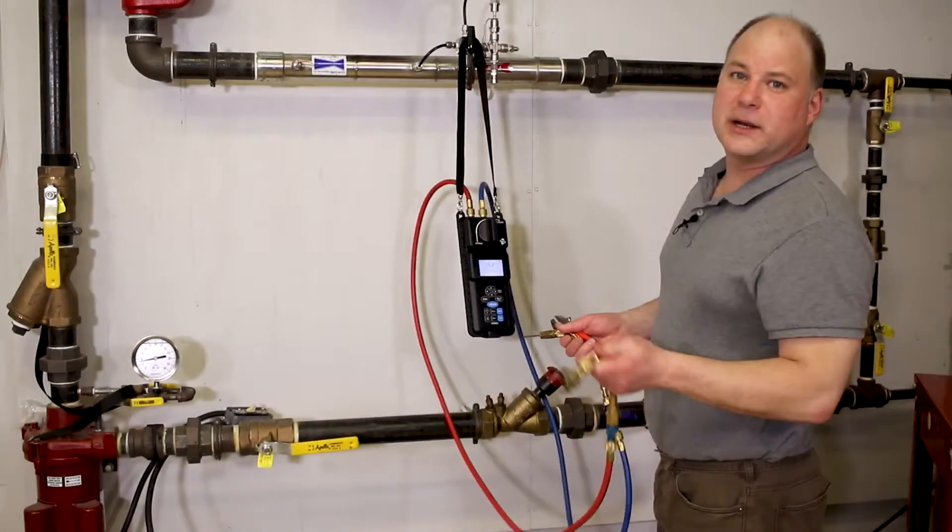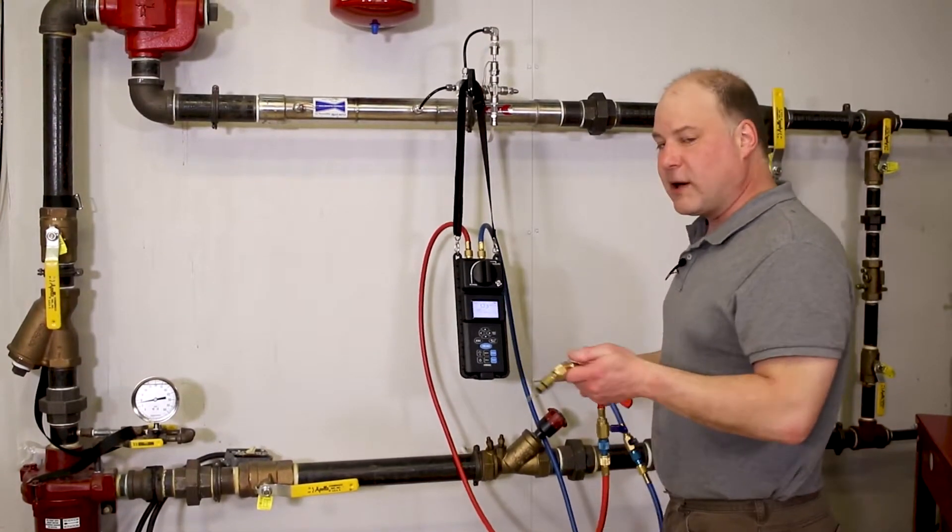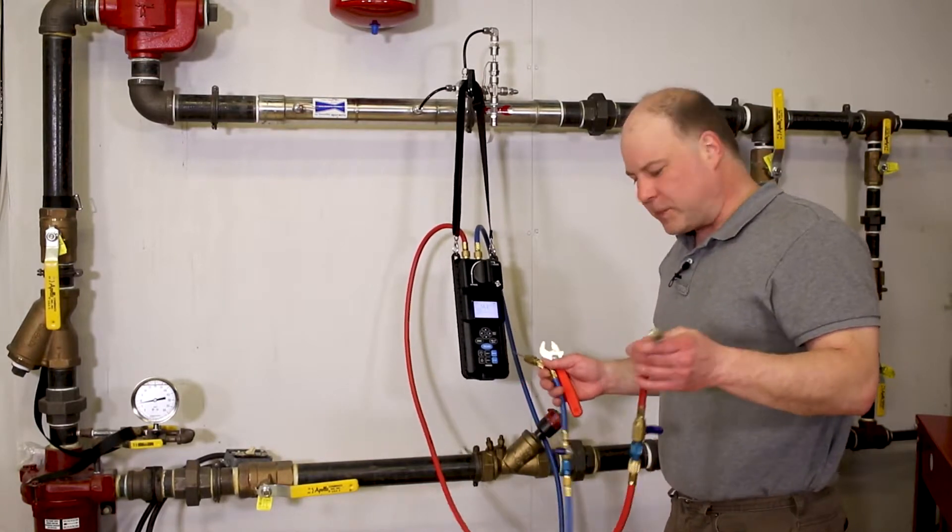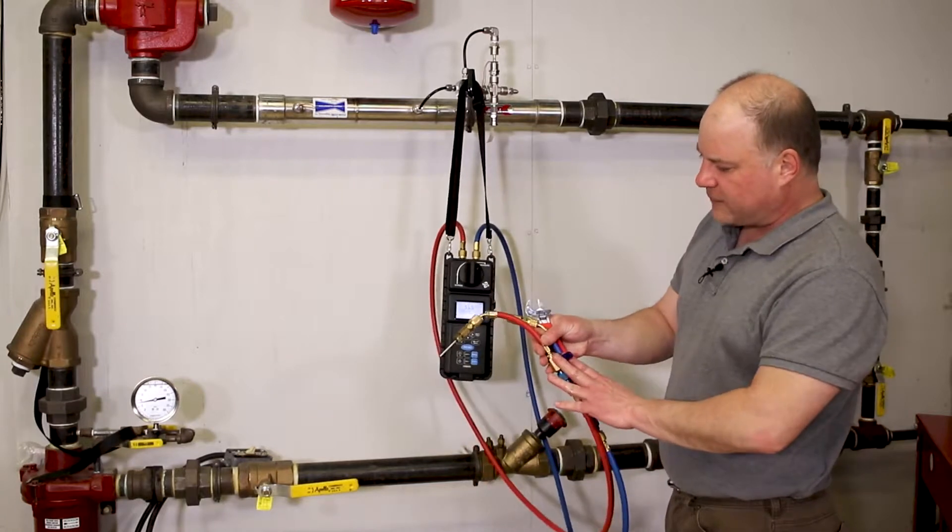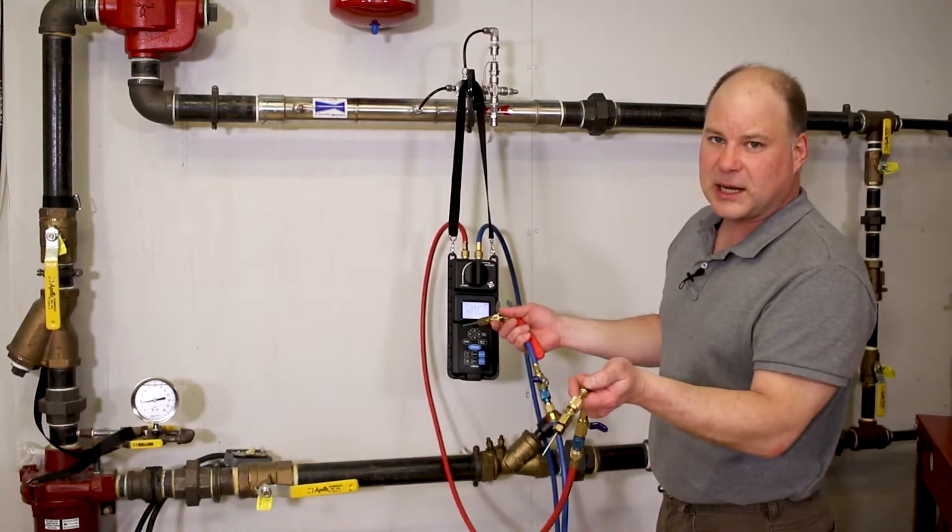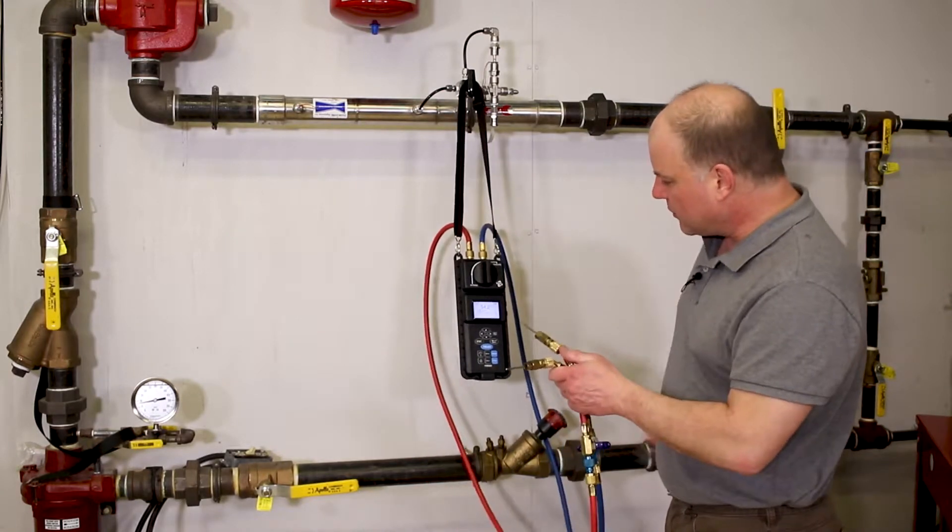Now we can go to another valve and repeat the measurement process. However, since we've already bled the hoses of air, there's no need to repeat that process. When we put the valves in the off position, there's a slight vacuum holding the water in here, so we shouldn't see any air inadvertently get into the hose lines.